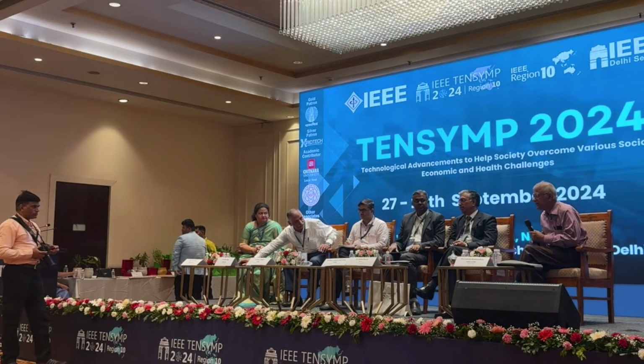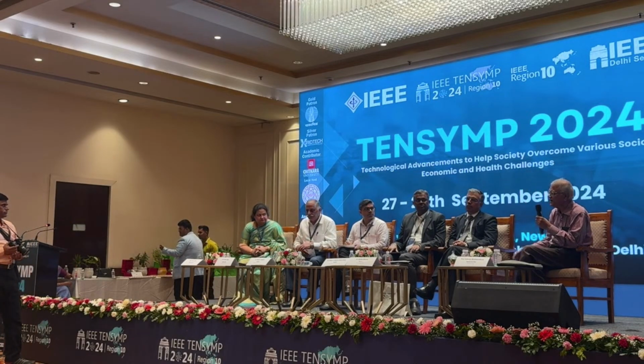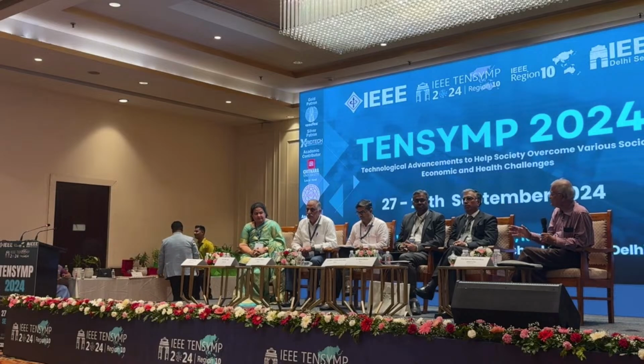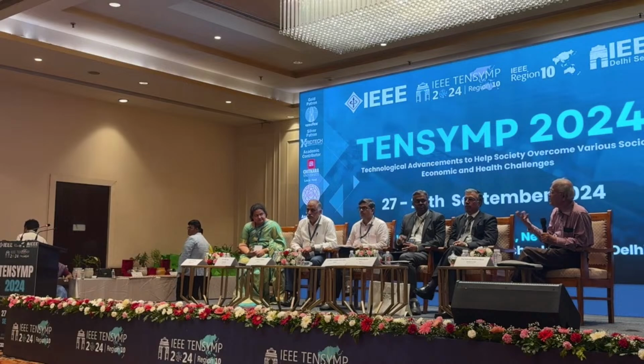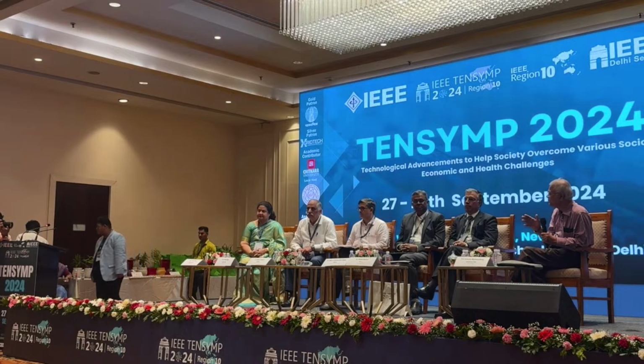Next point: we are transitioning from an AC dominated grid to partially DC, and in the process we are gradually losing inertia. As Samir mentioned, that May 2023 phenomena, or as Narasimhan talked about, losing 7,000 to 8,000 in the Rajasthan pocket itself, we saw that voltage recovery was not as expected because reactive power support through the inverter didn't come in time, there was a significant lag. That's a big issue, and finally we may reach, maybe after 50 years or so, a complete DC system.